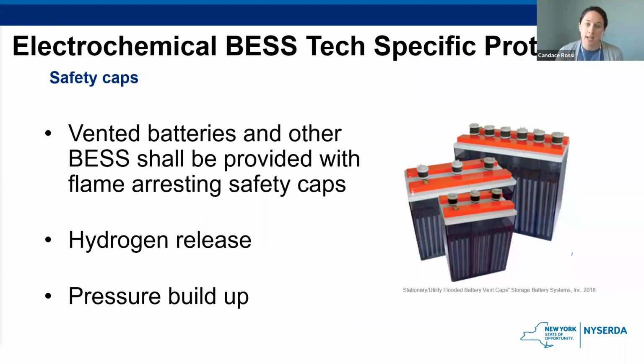So here we have the safety caps. So once again, this is not a requirement for lithium ion batteries. The safety caps are there because hydrogen is a byproduct of the charging and discharging process of some batteries, such as lead acid. So rooms or containers that have these systems should have a ventilation fan inside that will turn on when the flammable gas levels reach that 25% limit. And basically in valve regulated lead acid batteries, the gas is captured and then released when the pressure on the safety caps reaches a point that is considered overpressurized. So basically these caps will open and release the gas buildup.